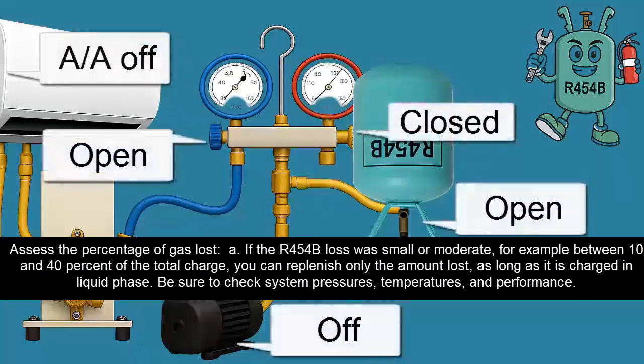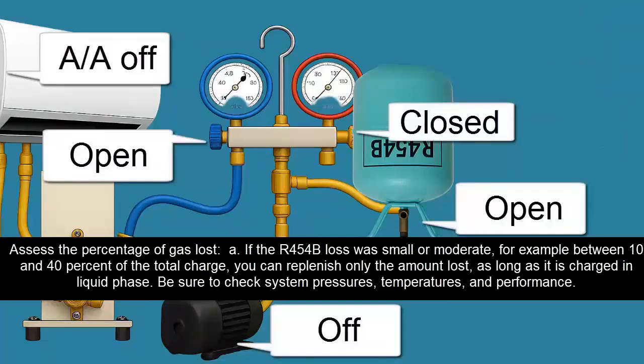Assess the percentage of gas loss. A. If the R454B loss was small or moderate, for example between 10 and 40% of the total charge, you can replenish only the amount lost, as long as it is charged in liquid phase. Be sure to check system pressures, temperatures, and performance.